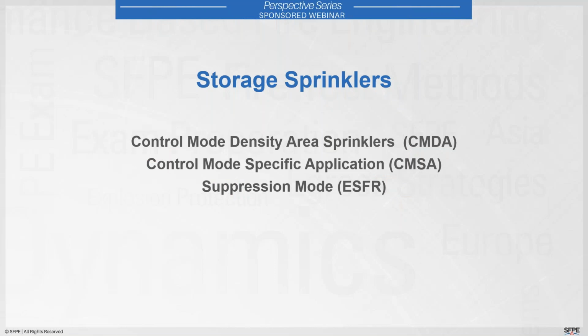So let's get into storage sprinklers. As I mentioned in reading NFPA 13, there are 3 chapters that cover the 3 types of storage sprinklers: control mode density area sprinklers, control mode specific application sprinklers, and suppression mode sprinklers, or ESFR.